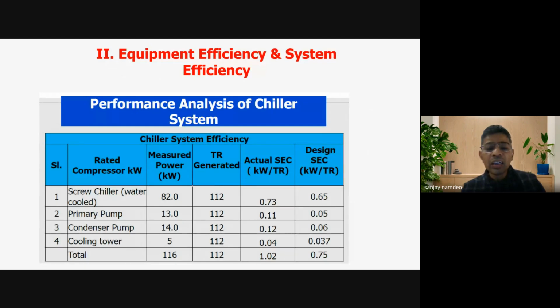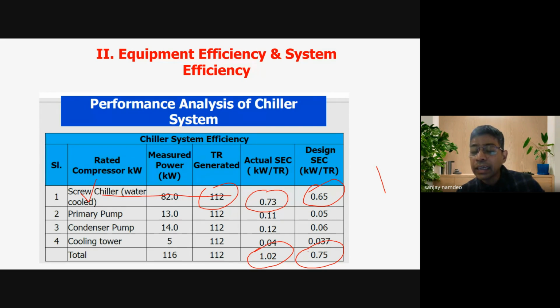Here you can see, this is the actual parameter. The chiller is consuming 82 kilowatt. It is delivering 112 TR, and there's an actual specific energy consumption and a rated or design specific energy consumption. Design is 0.65 and operating is 0.73. So this is for the chiller, right? Whereas if I see the system efficiency of the entire HVAC system, design is 0.75 kilowatt per TR, whereas operating is 1.02 kilowatt per TR.